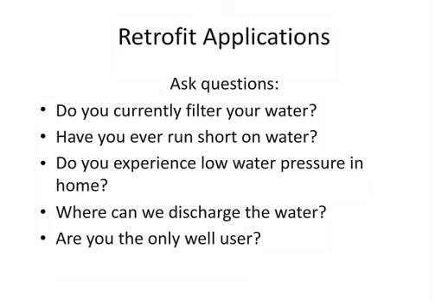Mr. or Mrs. Homeowner, have you ever run short of water? In other words, in a drier year where you don't get much rainfall, do you have an issue with the amount of water available to you? Always want to ask that question. Do you experience low water pressure in the home? Now, this is not necessarily indicative of the quality of water. It may be indicative of their delivery system, but believe you me, when you're going to install a geothermal heat pump, it's tied into their domestic water supply that affects their home.